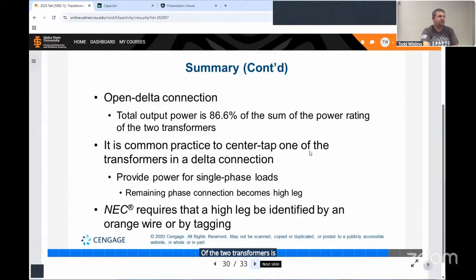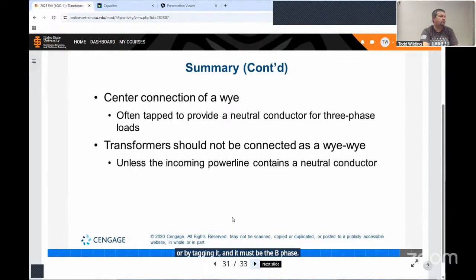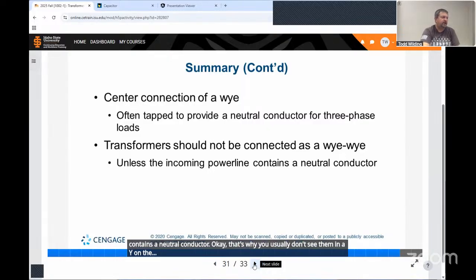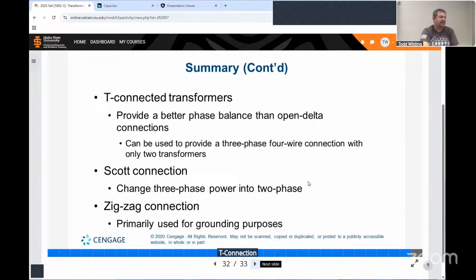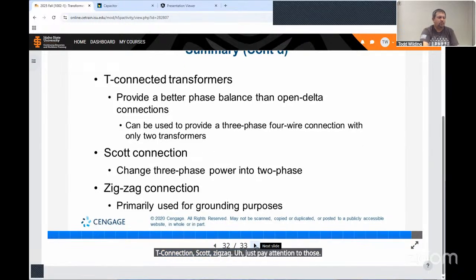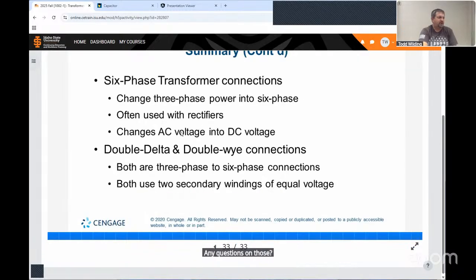It is common practice to center tap one of the transformers in a delta connection for your single-phase loads. Therefore, that's where you would get the high leg. Here's the requirement: the NEC requires that a high leg be identified by orange or by tagging it, and it must be the B phase. The center connection of a wye provides a neutral connection for a 3-phase transformer connected as a YY, unless the incoming power line contains a neutral conductor. Okay, that's why you usually don't see them in a Y on the power side. T connection, Scott, zigzag. Just pay attention to those. Any questions on those? And the 6-phase and the delta or double Y connections.